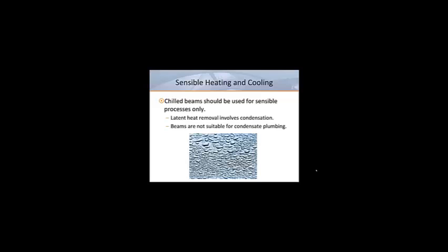Chilled beams should only be used for sensible heating and cooling. They can raise or lower the air temperature of a room, but they cannot remove moisture from room air. Humidity reduction is a latent process that involves condensation. Since a chilled beam is located in a room, usually at or just below the ceiling, it is unsuitable for condensate piping.